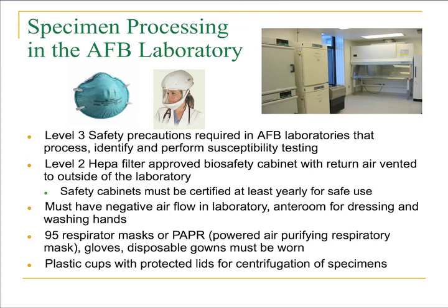You must also have negative airflow in the AFB laboratory, and an anteroom for dressing, changing, and washing hands. While working in the laboratory, you must wear either an N95 respirator mask or what's called a PAPR, a powered air purifying respirator, which is pictured on the right-hand side of this photograph. You must also wear gloves. Disposable gowns must also be worn. In case there is a spill onto your gown, you must be able to remove it quickly and put it into a biohazardous container. Plastic cups with protected lids must also be used for centrifugation of your specimens.